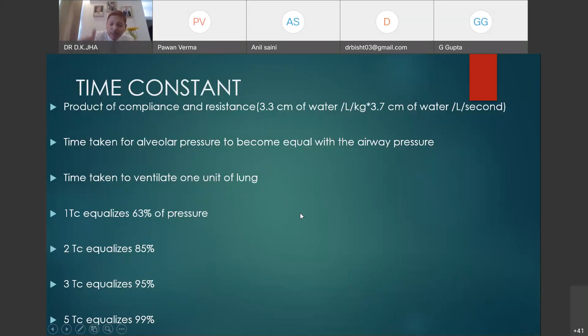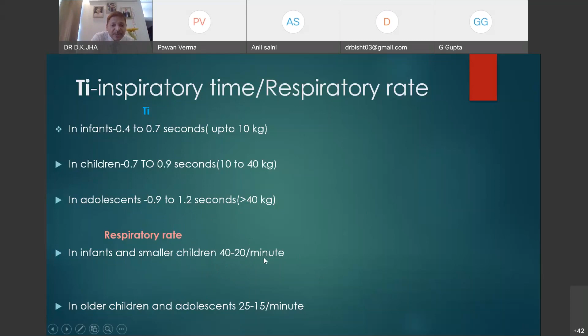Normally, if you don't want to do this calculation, just remember that in infants Ti is 0.4 to 0.7, in children 0.7 to 0.9 seconds, in adolescents 0.9 to 1.2 seconds. Set this, and set the respiratory rate in infants and small children at 40 to 20. See, I have put it in reverse. Usually in books it is written 20 to 40 and 15 to 25. Why have I written it in reverse order? Because as age increases, respiratory rate decreases. So as the age of your child increases, decrease the respiratory rate accordingly. You set the respiratory rate on the ventilator.